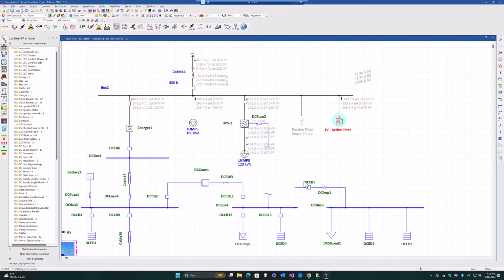Of course, you can increase the size of the filter by putting another one in parallel to get more current to achieve a better power factor in terms of reactive power control. You can also activate things such as load balancing and unbalanced compensation. Though we are at the limit, the filter is going to do its best to adjust its per phase output to balance the unbalance in the system as best as it can, but it has pretty much reached its limit. The point was to show you that the active filter works as a power conditioning system in the unbalanced based modules. But of course, its true power is activated when we go to unbalanced harmonics.